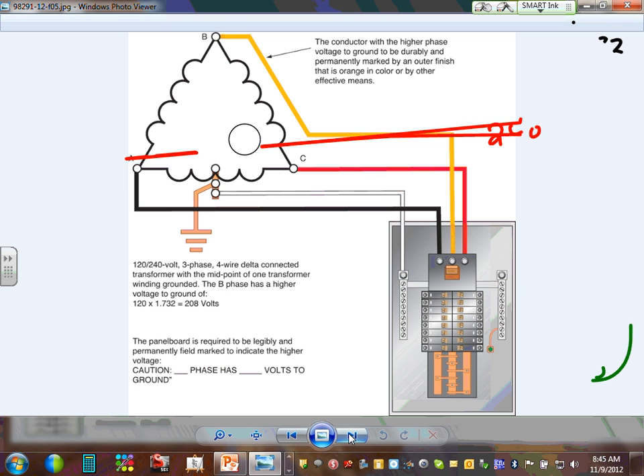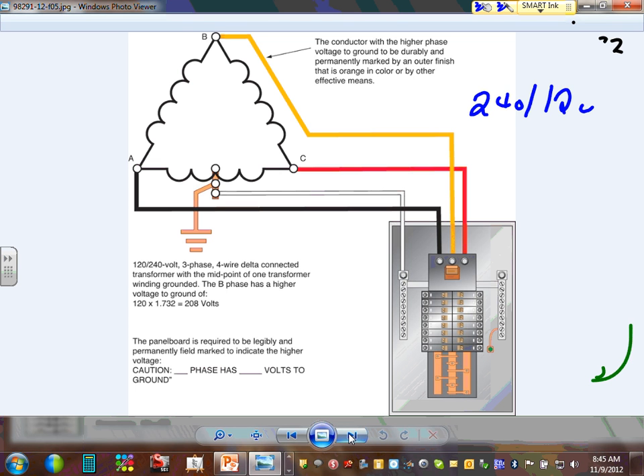Be aware that this can be used in certain commercial buildings. This system is called 240. Oops, not 480, Chad. 240. This system is 240/120 3-phase. This is the only way you can get 240/120 3-phase. The one and only way. This is called the center tap delta. Can you guys see where they take the delta here, the center tap? This is called the wild leg. Remember that wild leg, high phase leg? The voltage between here and the neutral, anybody remember? 208 volt. So that's why they call it wild leg.